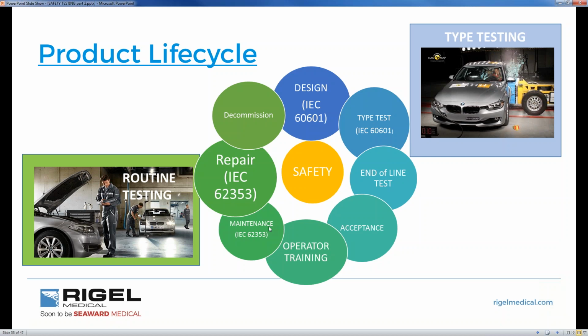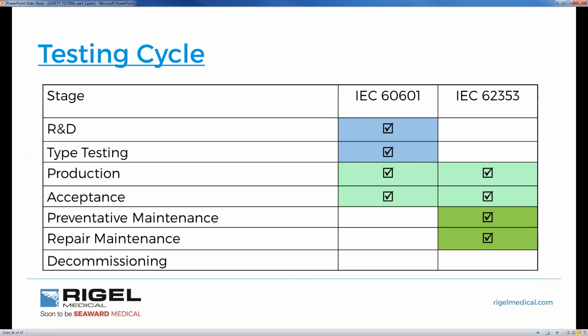As far as I'm concerned, my role within Rigel is to educate guys around the world to get rid of 60601 testing and adopt 62353, because adopting 62353 has been totally designed. The purpose of the standard is for preventative maintenance measures. That's how we should be using 62353. 60601 is for the R&D guys, the manufacturers. 62353 is for the clinical engineers, the biomeds that want to make sure medical devices are safe to use in a healthcare environment. So you've got the set data.